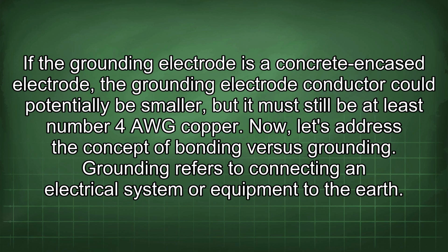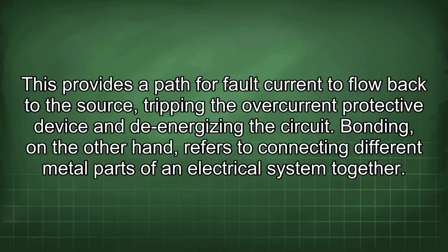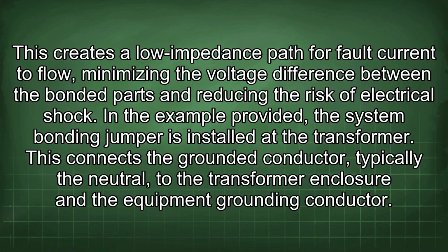Now let's address the concept of bonding versus grounding. Grounding refers to connecting an electrical system or equipment to the earth. This provides a path for fault current to flow back to the source, tripping the overcurrent protective device and de-energizing the circuit. Bonding, on the other hand, refers to connecting different metal parts of an electrical system together. This creates a low impedance path for fault current to flow, minimizing the voltage difference between the bonded parts and reducing the risk of electrical shock.